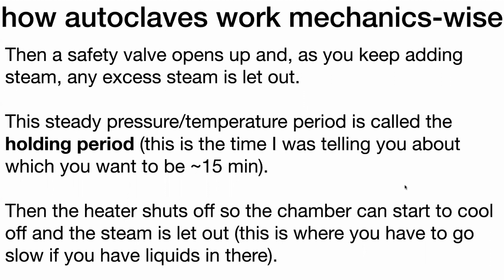And so a safety valve is going to open up. This way, if you add excess steam, that excess steam is going to get let out. And you reach this period that you call the holding period, where you have a steady pressure and temperature. This is a time that you want to make sure is at least 15 minutes or so. Although you only typically need about 15 minutes to get that basic sterilization, this actual cycle is going to be a lot longer because you have to have that buildup of the pressure, and then afterwards, you have to have that release.